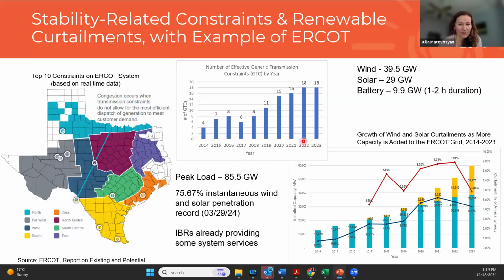This is concerning because it in turn causes curtailment of renewables. You have cheaper, cleaner sources of power in the west part of the grid, but because of transmission constraints, you cannot transfer it to load centers, so renewables get curtailed this way. You can also see peak load in ERCOT is 85.5 gigawatts.